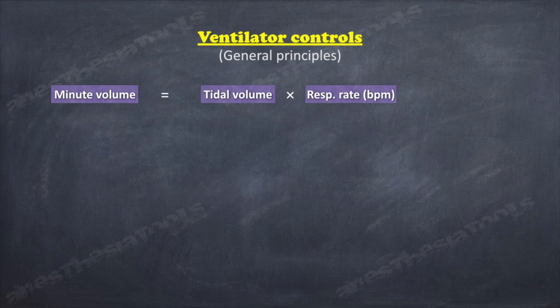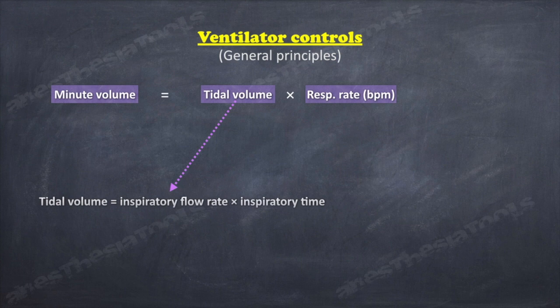For control ventilation, the equation can have only two user-defined variables, the third being dependent on the other two. The tidal volume is derived from the inspiratory flow delivered by the ventilator and the time over which this is delivered.